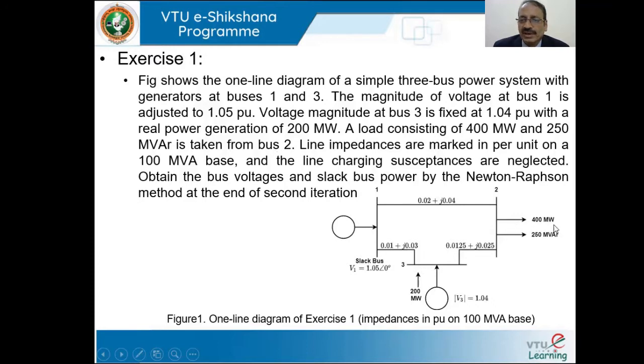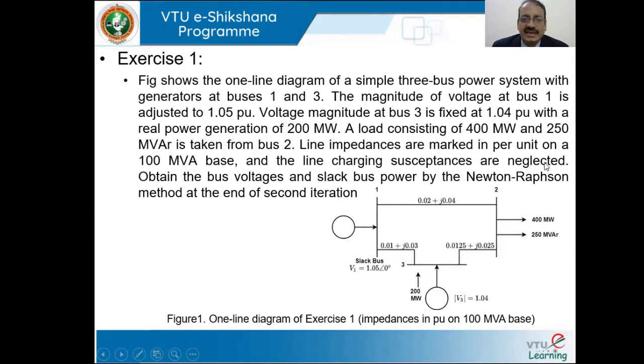A load of 400 megawatt and 250 MVAR is connected to bus 2, which draws 400 megawatt active power and 250 megavolt-ampere reactive power. Line impedances are marked in per unit: line 1–2 has impedance 0.02 + j0.04, line 1–3 has 0.01 + j0.03, and line 2–3 has 0.0125 + j0.025 per unit. Line charging susceptances are neglected. We are asked to find bus voltages and slack bus power by the Newton-Raphson method at the end of the second iteration.